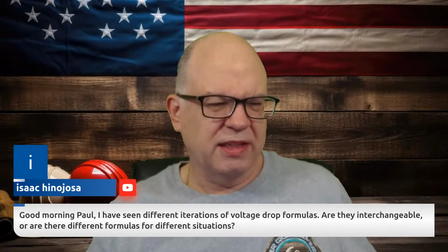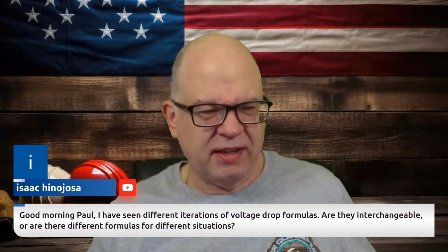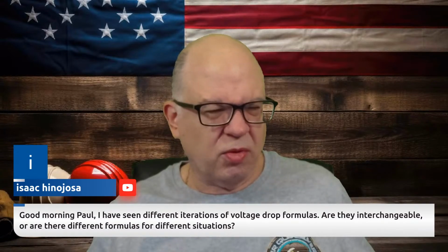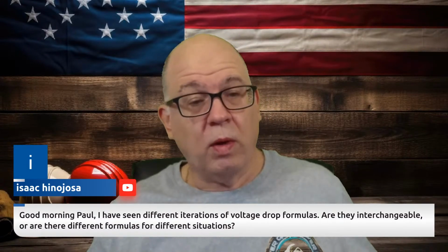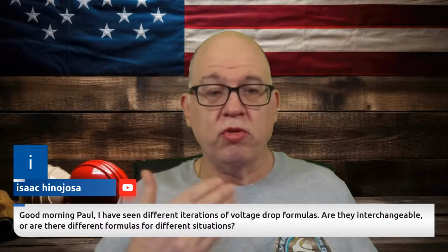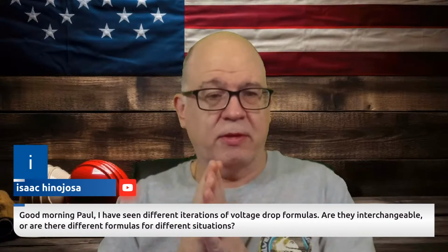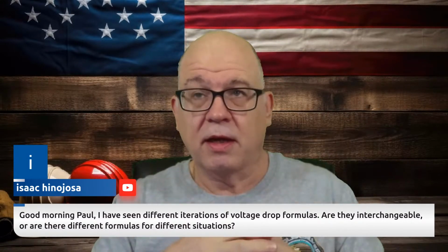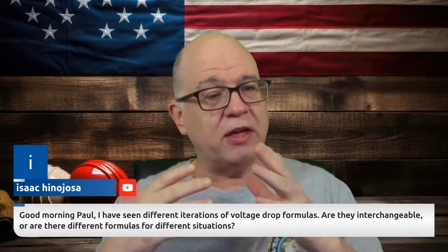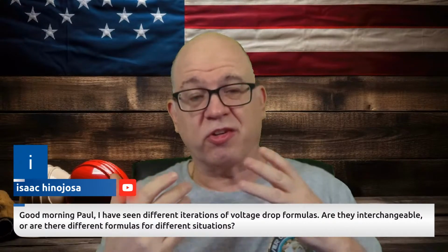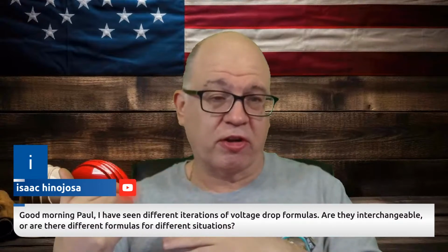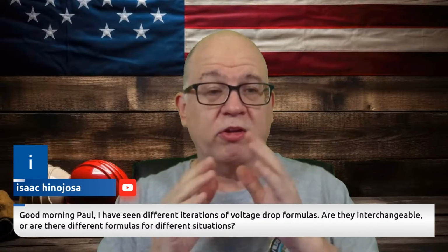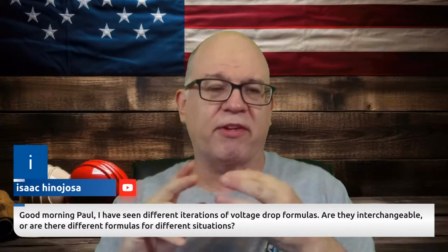Let's see here. Good morning, Paul. I have seen different iterations of voltage drop formulas. Are they interchangeable, or are these different formulas for different situations? Well, it depends. You have voltage drop depending on what you know, for example, right? You need to know certain things. So we need to know the distance one way. We need to know what the load is at the end. And one of the differences is we can use voltage drop calculation to determine what conductor size we need. So you're plugging in circular mils and exchanging circular mils and things like that, depending on what you're trying to find. So yes, you have multiple formulas depending on what variables you know.